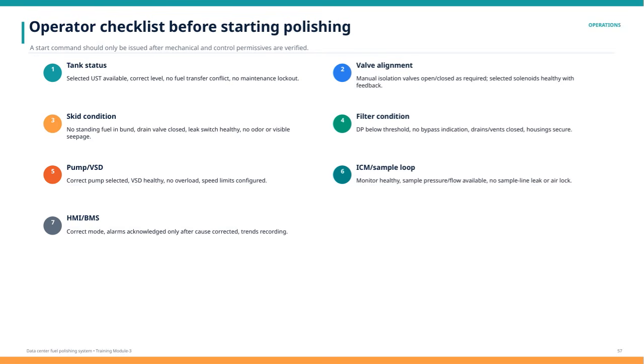Moving on, evaluate the filter condition. Differential pressure should be below the threshold. There should be no signs of filter bypass, and all drains, vents, and housings must be securely closed. The pump and variable speed drive require attention as well. Confirm the correct pump is selected. The VSD is healthy with no overload issues, and speed limits are properly configured.